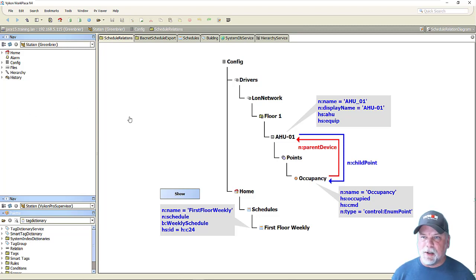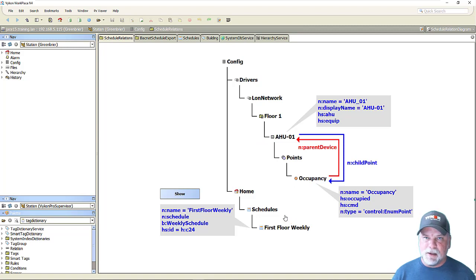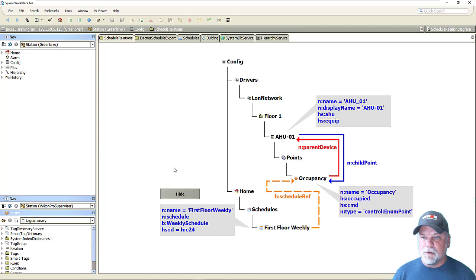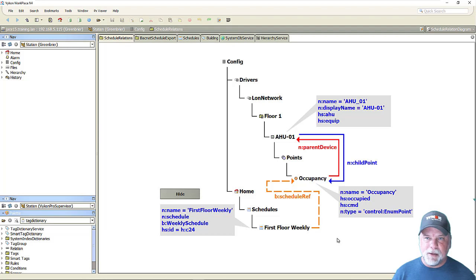In the first video, I go through and explain about using smart tags and relations to set up a relation between schedules and control points which are linked to the schedule. With this PX view, I'm showing a device under a Lon network that has an occupancy point, and that occupancy point is somehow linked to this first floor weekly schedule. The implied relation with the smart tag rule will go through and create an implied relation — the B colon schedule ref relation — which allowed us to more easily display things in PX and in hierarchies to show the equipment that was being controlled physically by the schedule.